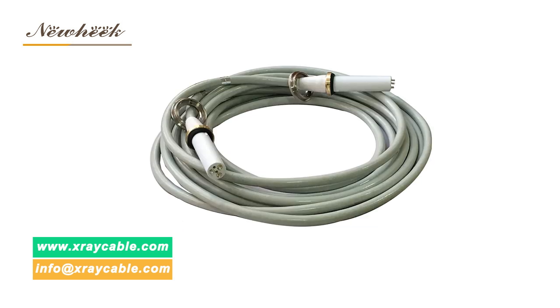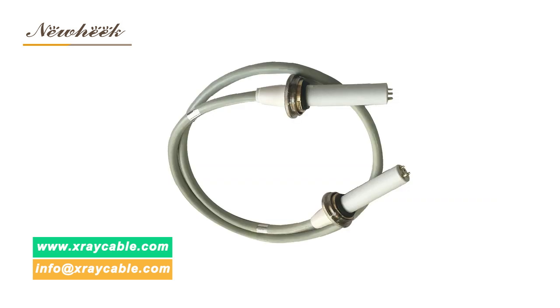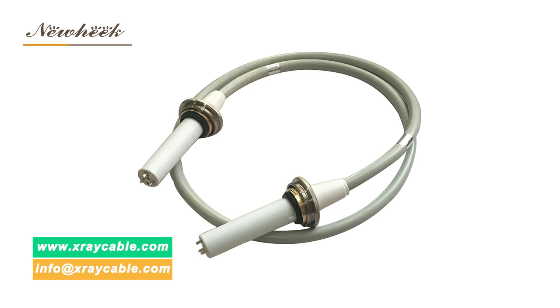Can Newheek's high voltage cable be used on the U-Arm? The answer is yes. The high voltage cable on the U-Arm can be used with Newheek's 75 kV or 90 kV high voltage cable. The choice between 75 kV or 90 kV depends on the data of the U-Arm tube.